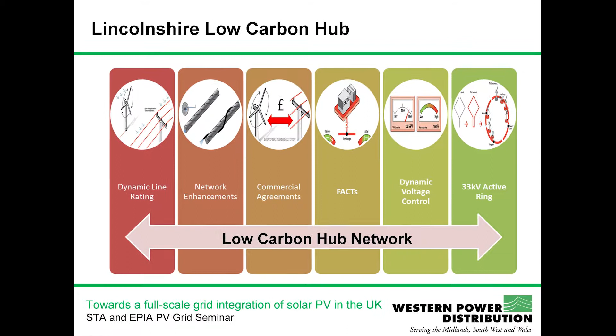So we entered this in the Low Carbon Network Fund with 6 different techniques to see how new generation can connect and how we can change the distribution network to lessen the impact of DG. 6 main techniques, the first of which is dynamic line rating. Our overhead lines operate with fixed summer and winter asset ratings, and we're looking to see how we can actively calculate these ratings to fit more generation to that network during times when it is colder and when it's windier.